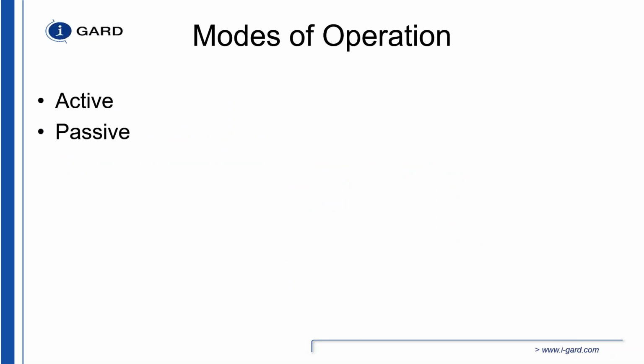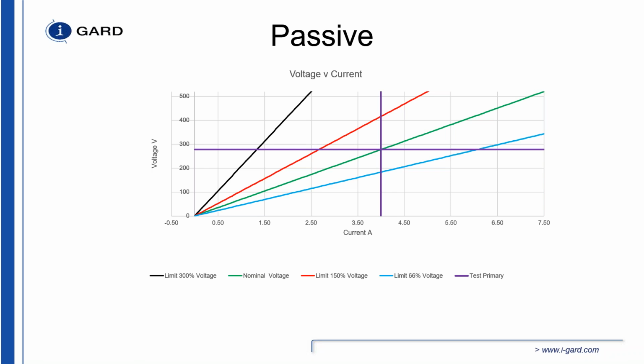So one competitor says the power circuit elements, other than those connected for the purpose of connecting a power system to ground, are often not compatible with these elements. These include single phase grounding transformers and grounded Y primary potential transformers. So one of my competitors cannot do this because they don't know how, and we do it a different way, so we can. So getting into the way we monitor the integrity of the resistor, there are two methods, active and passive. Let's discuss the passive way first.